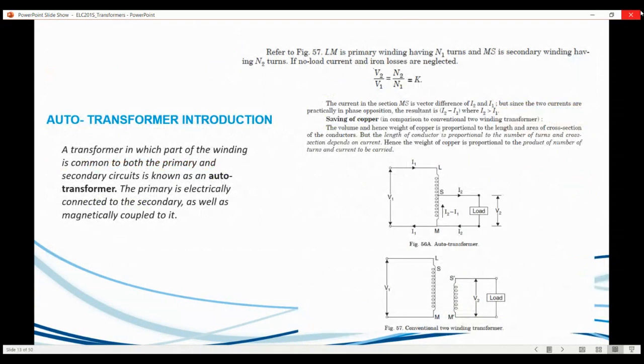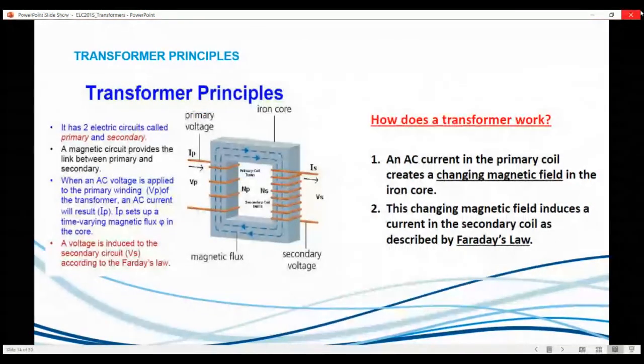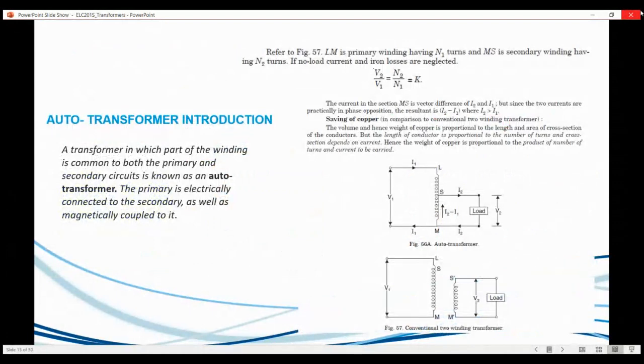You also have something called the auto transformer. You'll start to hear about it when I call upon you. This is basically when your winding is common to both the primary and secondary side. If you have a look at that, it's essentially one winding instead of two different windings. The primary is electrically connected to the secondary as well as magnetically coupled to it. The auto transformer is typically used for starting motors, especially bigger size motors, which we'll talk about in Electros 3. And obviously you save a lot of copper when using an auto transformer.